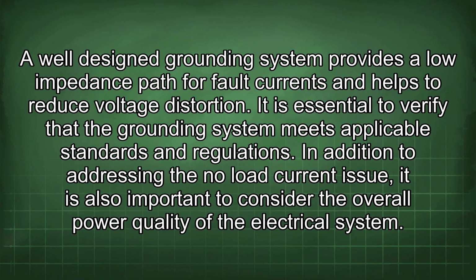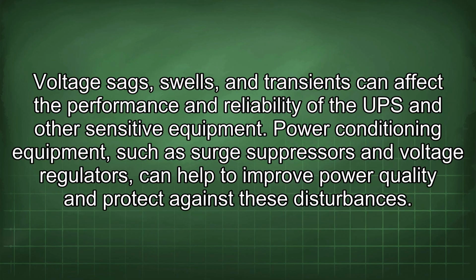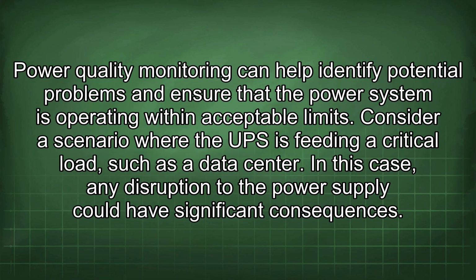In addition to addressing the no-load current issue, it is also important to consider the overall power quality of the electrical system. Voltage sags, swells, and transients can affect the performance and reliability of the UPS and other sensitive equipment. Power conditioning equipment, such as surge suppressors and voltage regulators, can help to improve power quality and protect against these disturbances. Power quality monitoring can help identify potential problems and ensure that the power system is operating within acceptable limits.